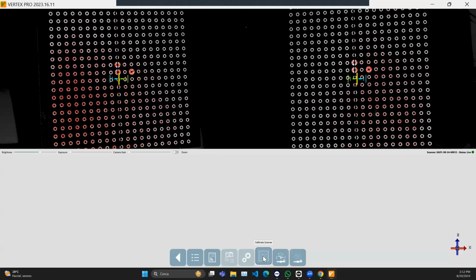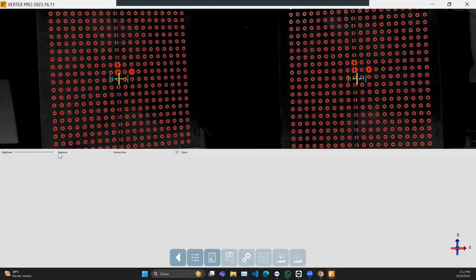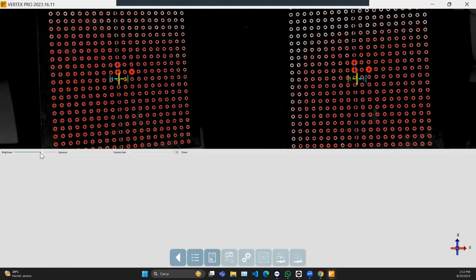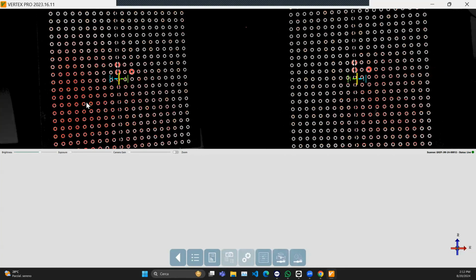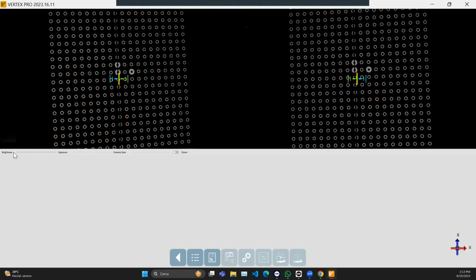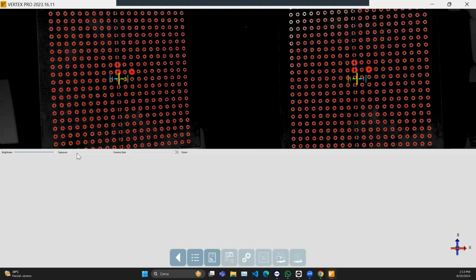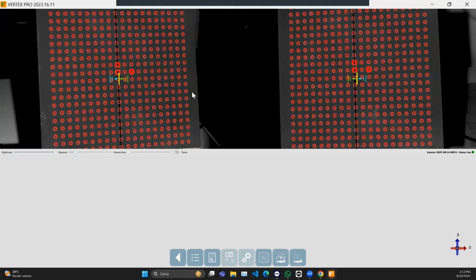The first calibration we do is the 2 cameras calibration. If we do that using the black calibration plate, we have to set the quantity of light in order to see a good condition. Good condition for us is not a lot of red on the images. Red means saturation. So we have to stay in the middle between the gray, where the white is gray at the end, and where the black is gray.